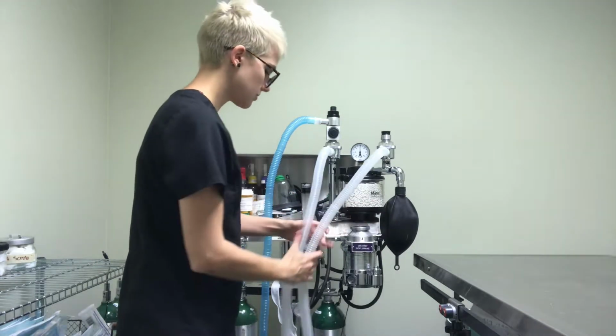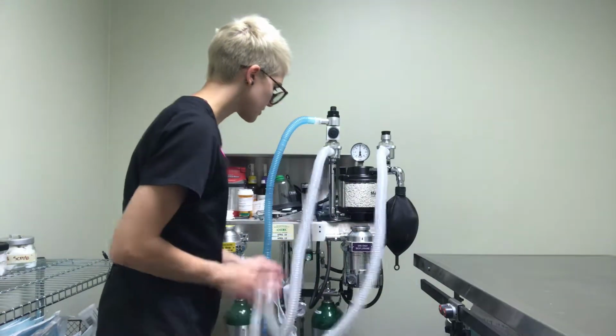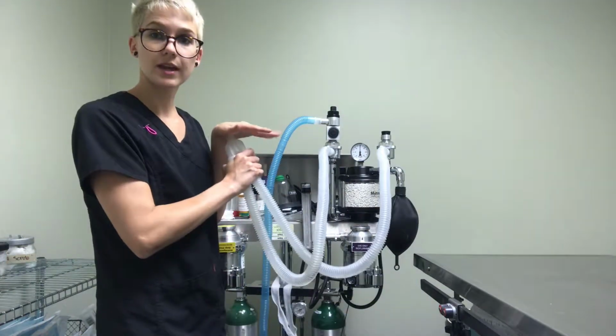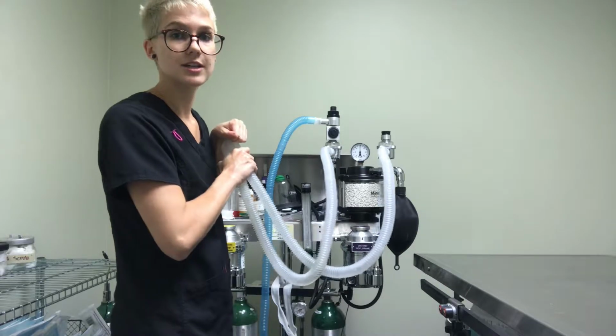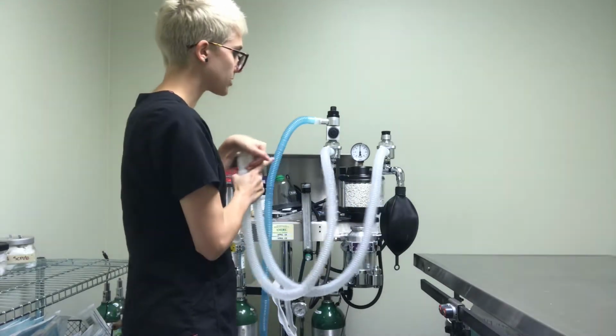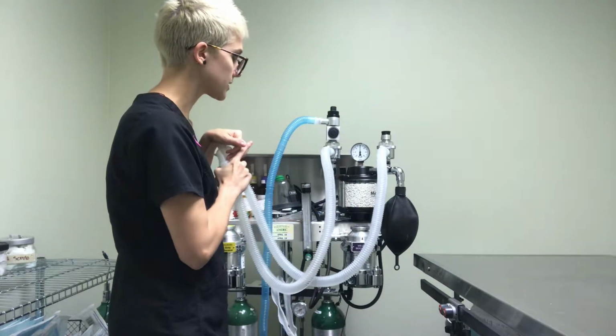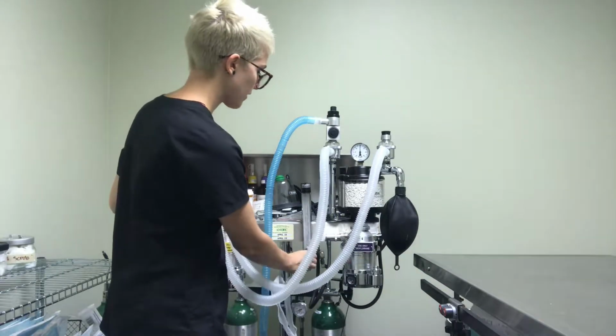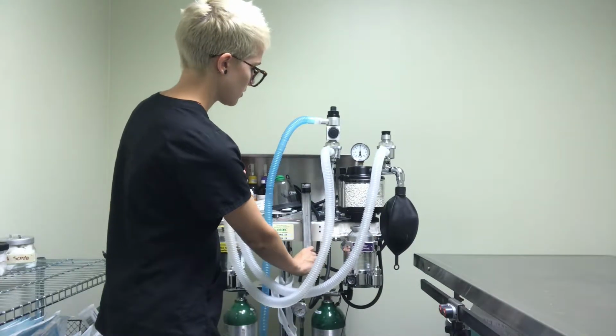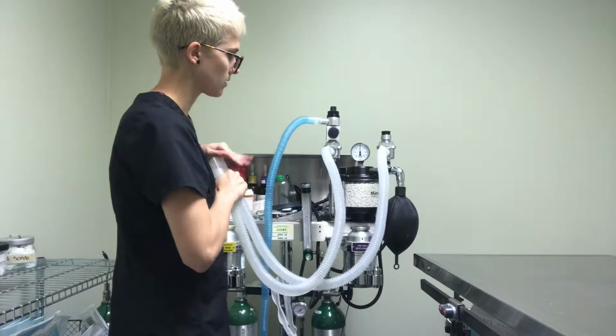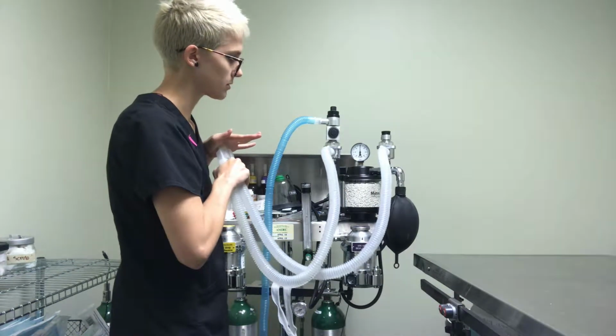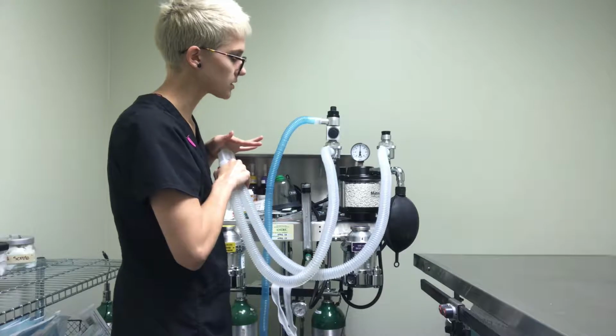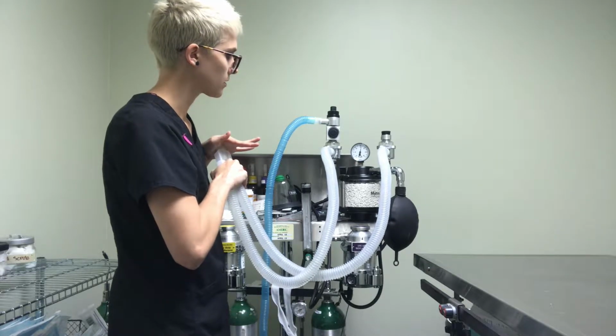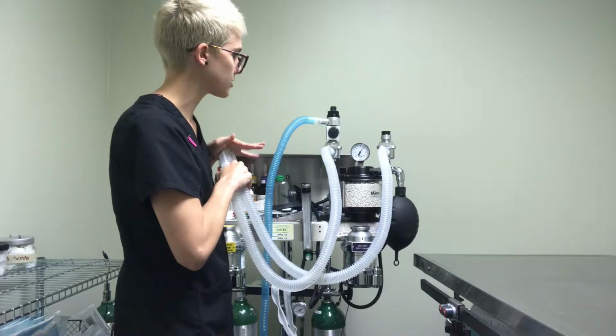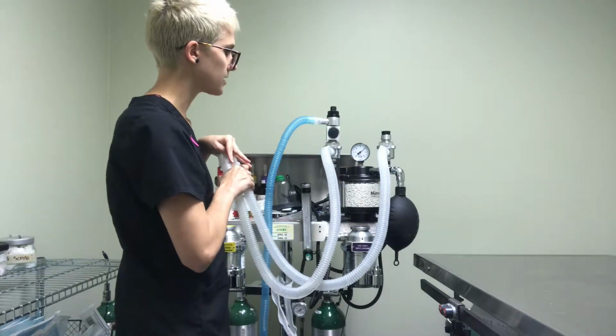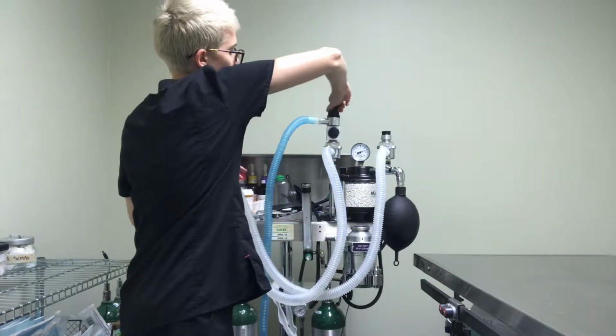Then what I'm going to do is turn the oxygen on. I'm going to put the palm of my hand over this so that no oxygen can leak out over here. Then I'm going to watch the manometer till it reaches 20 and watch the bag fill up. So make sure the bag is filling up, and it is. And the gauge is starting to reach 20. And then once it does, I'm going to open the pop-off valve.